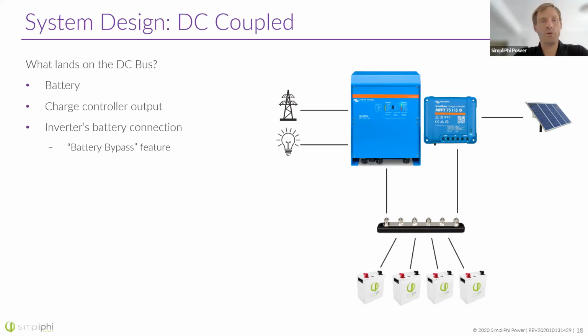Well, you'll have an inverter, what we're showing here, some Victron equipment. You've got a grid, and that grid can come into the inverter. That inverter can communicate with a charge controller. This is a smart charge controller here. Victron has an app that you can use to regulate your charge controller and your inverter. The charge controller will bring the solar array in. The connection, the power connection between the charge controller and the inverter is through the DC bus. And so we land our batteries on the DC bus. The charge controller lands on the DC bus, and the inverter lands on the DC bus, and then your loads come out of the inverter. And so this is a very typical simple DC coupled design.